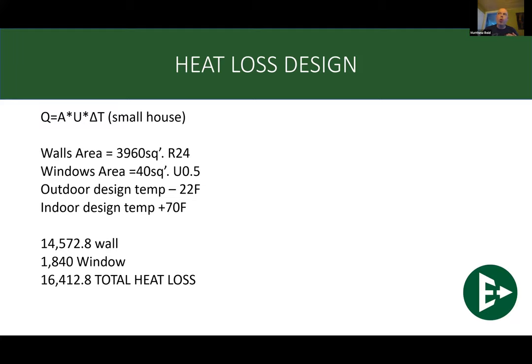And then my home was renovated in 2014 to change the R value of the walls to R24. I have a total window area of 40 square feet, and my U value of that is 0.5. The outdoor design temp, again, it's not here for Barry, but that is just a design number here. We're doing minus 22 Fahrenheit. Indoor design temperature is plus 70.